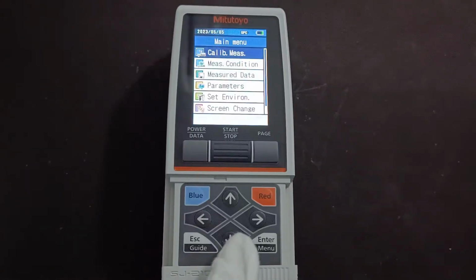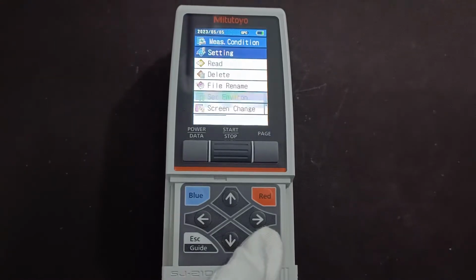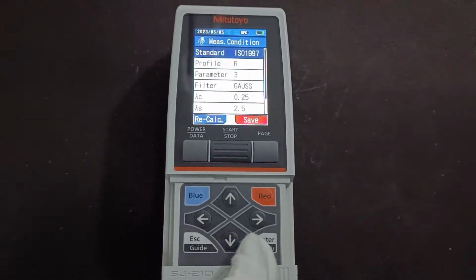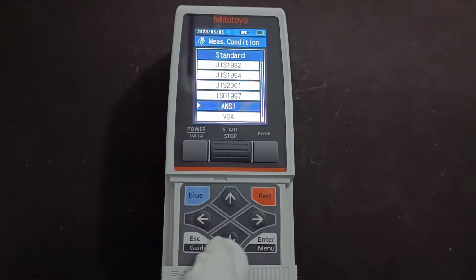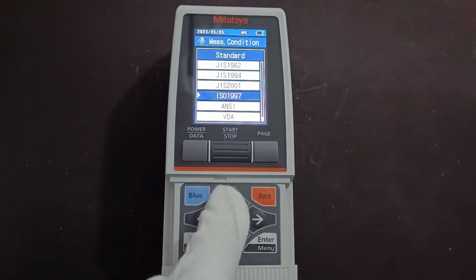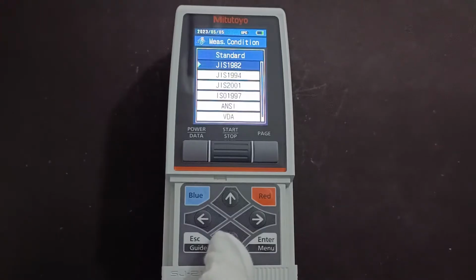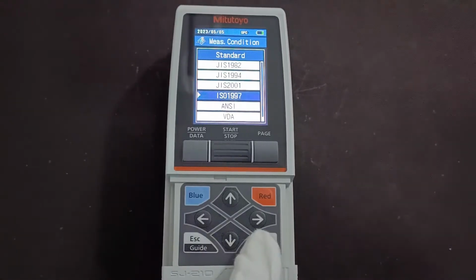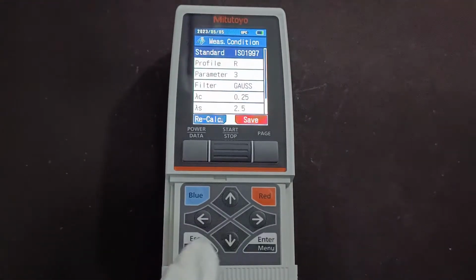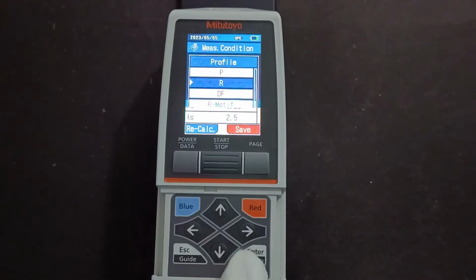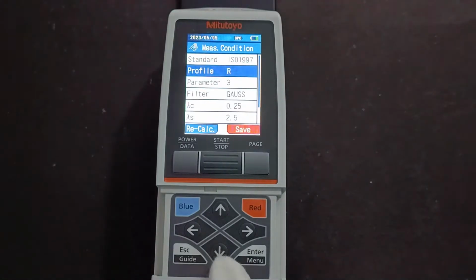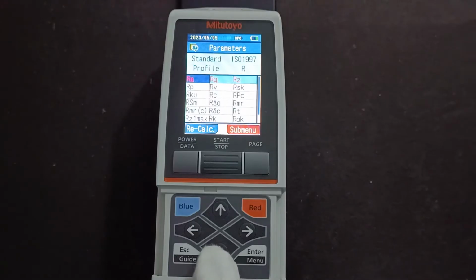The next option is measure condition. In that, press settings. Let's see every condition in detail. In standard, there are various standards like JIS, ISO, ANSI, etc. Select the roughness standard as per your requirement. I have selected ISO 1997. The required evaluation profile can be selected. In parameters, Ra, Rq, Rz or any other parameter can be customized.